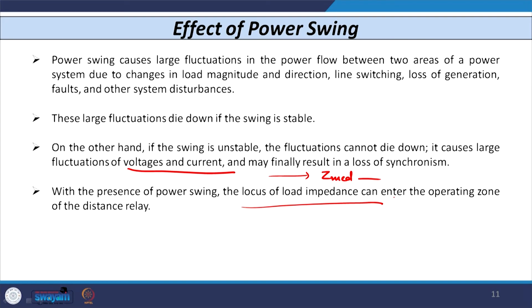Whenever the power swing phenomenon occurs, the current increases, so any overcurrent relay may not operate correctly. In case of power swing, voltage also reduces, so any voltage based relay also does not operate correctly. In case of frequency deviation, a digital distance relay also measures the wrong value because it is based on phasor calculation. The phasor calculation may not be correct, and hence the digital relay may also maloperate.